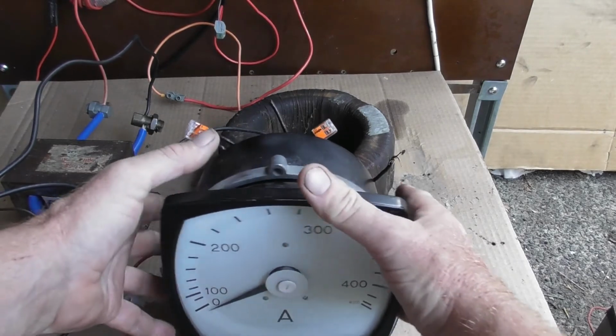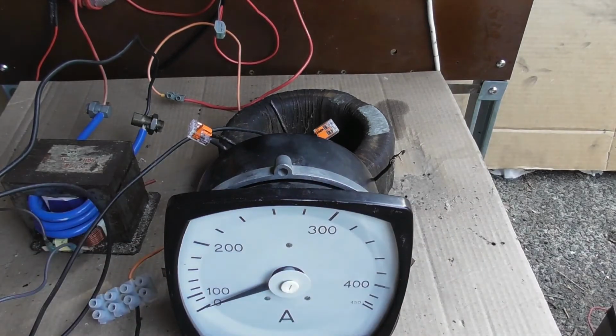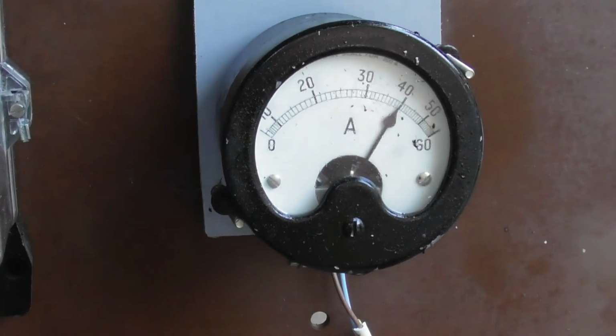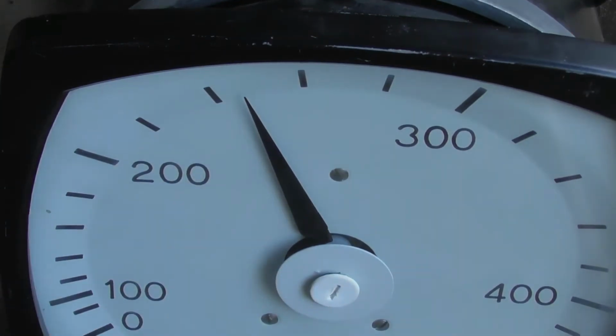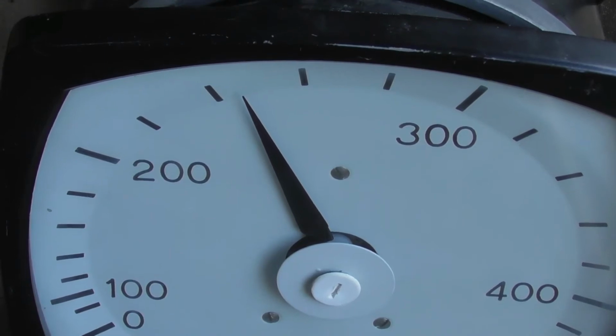So I'm going to energize this device again, and I'll leave it all running in one go. I haven't changed any settings on the variac, so I see there's a bit of a pop back there. That's a lot lower - I need to take more turns off. The current has picked up because there are fewer turns on the primary, so that's sitting at 40. This one sits at about 240 amps, so I probably need to take another 3 turns off.